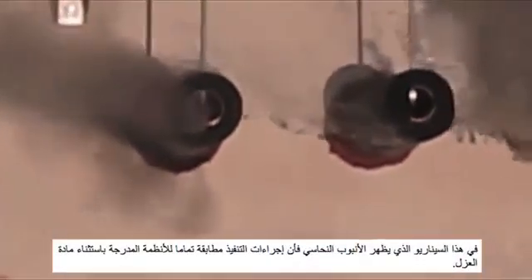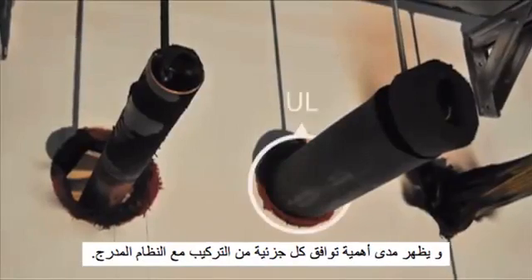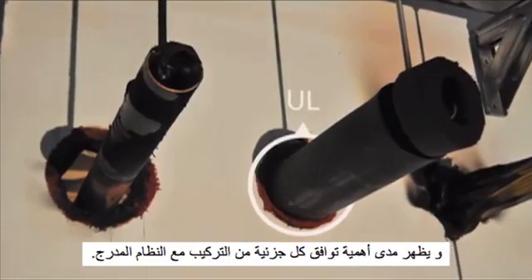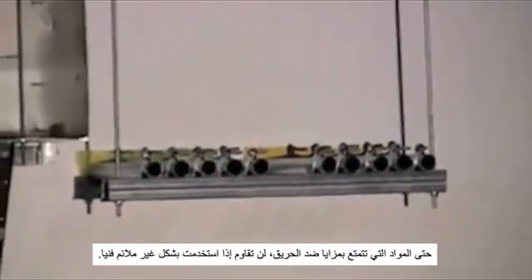In this scenario showing a copper tube, the installations are identical with the exception of the insulation material. Use of the non-compliant insulation results in rapid spread of fire and smoke and demonstrates the importance of matching every detail to the listed system. Even materials with respectable fire properties will not hold up if used inappropriately.